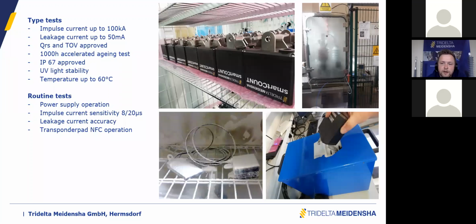One slide I want to show you, which was asked about very often yesterday, is: what type tests have you performed? What routine tests are you running? So just to give you a little background of what we have done. Of course, we have done the typical voltage or electrical tests. We also do tests on our surge arresters. The devices installed on the surge arrester should have the same performance as the surge arrester.